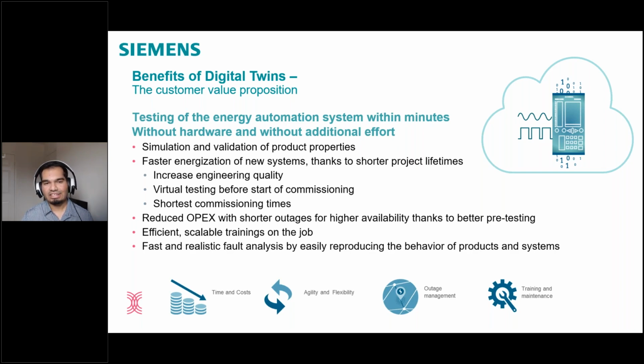You foresee any challenges you would meet before commissioning, you would meet while doing the testing at that point of time, and hence it would result in shorter commissioning time. Since you're already well prepared beforehand, it will result in shorter commissioning times, better quality, and quicker resolution of issues. Then you have reduced OPEX with shorter outages for higher availability thanks to better pre-testing.